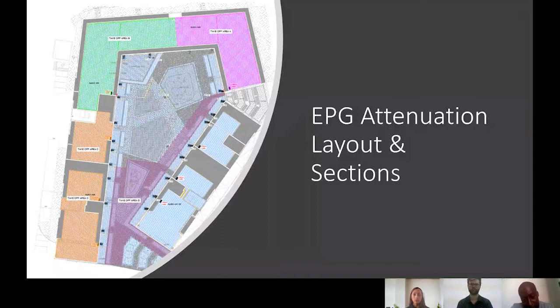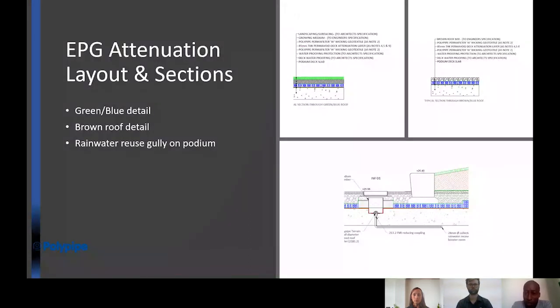On this particular layout drawing you'll notice squares around the edges on the podium. Once water is flow-controlled off the roofs, it enters a filter chamber on the podium itself before entering the wider raft. This is important as a maintenance point — we have a sump within those chambers which collects heavier debris, and the water is filtered before it enters the system. The chambers also provide a 3D maintenance point at each stage on the podium where rainwater pipes discharge.